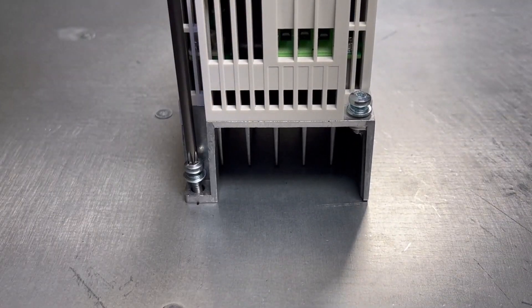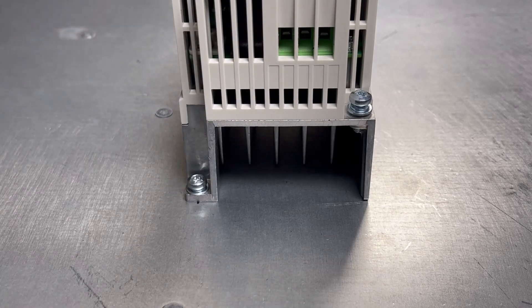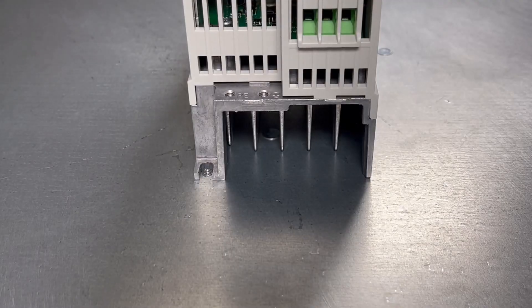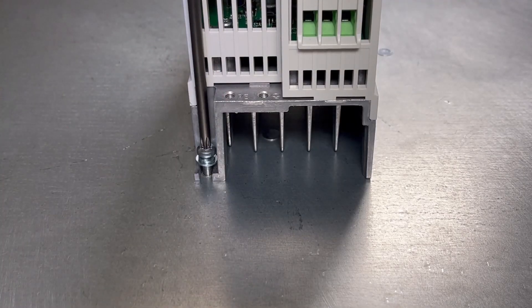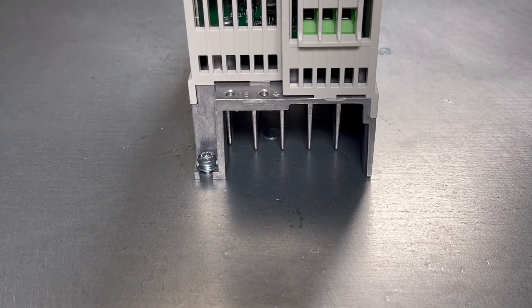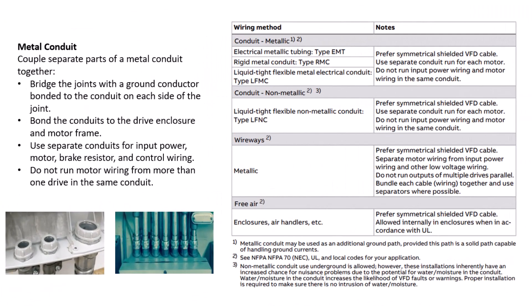Third, attach the drive to the mounting holes using the provided hardware and torque the hardware to spec according to the values listed in the Quick Installation Guide and Hardware Manual. Run the supply power, control, brake resistor if applicable, and motor cable connections to the drive enclosure through their own individual metallic conduits.